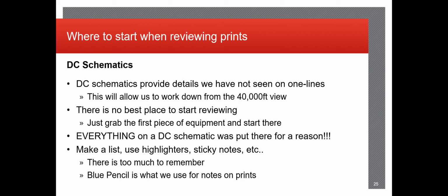So where we start when we're reviewing prints usually is with DC schematics. That's where we'll find details that we haven't seen in one line, since one line is just the bigger picture usually. DC schematics are the nitty-gritty ins and outs of all the protection equipment, any other equipment that may be in the control house, or even in equipment cabinets out in the yard, such as breakers or CCVTs, which are capacitive coupling voltage transformers.